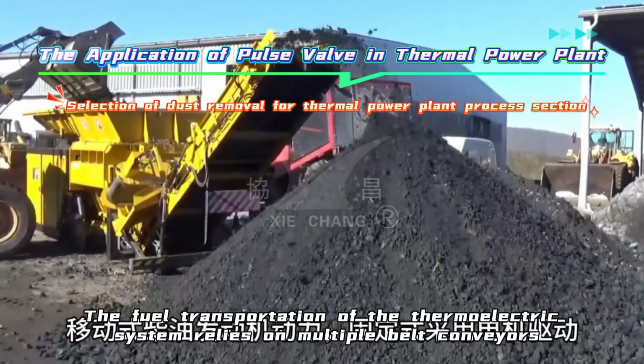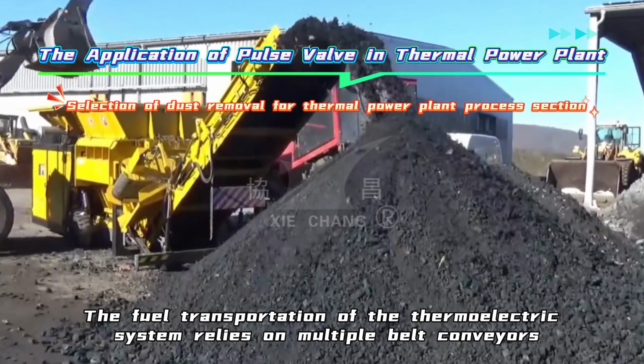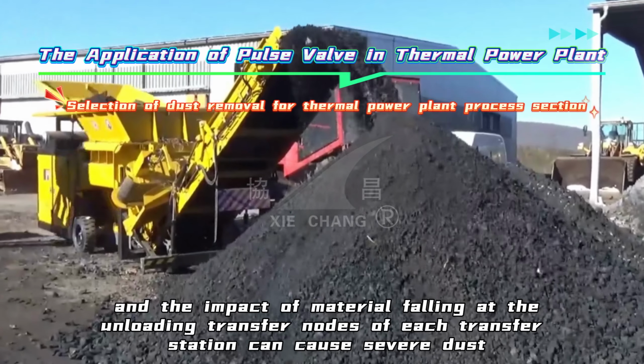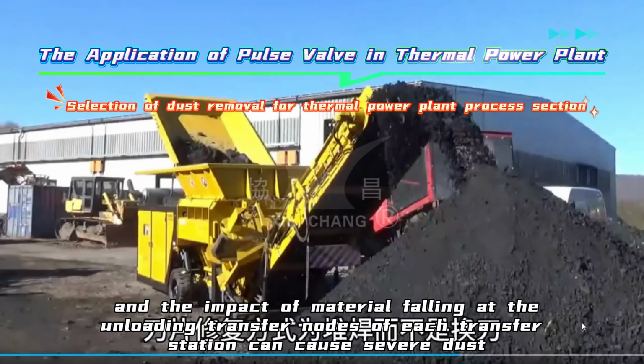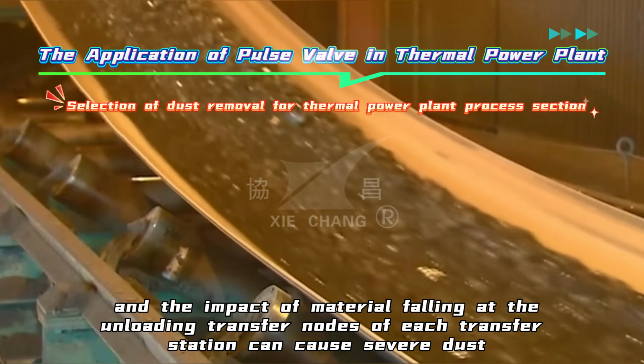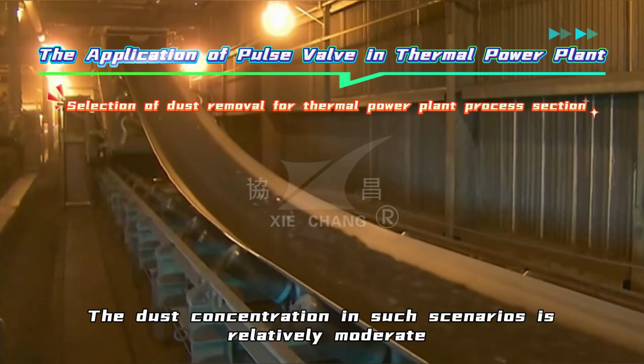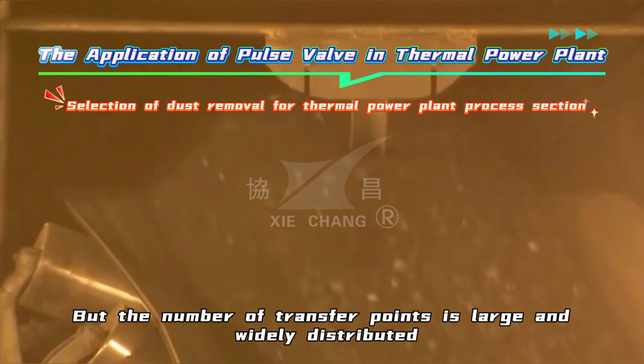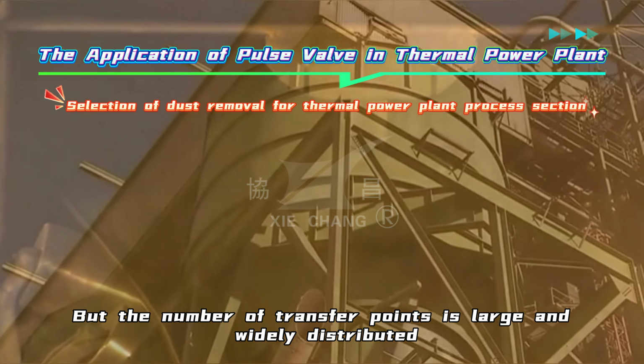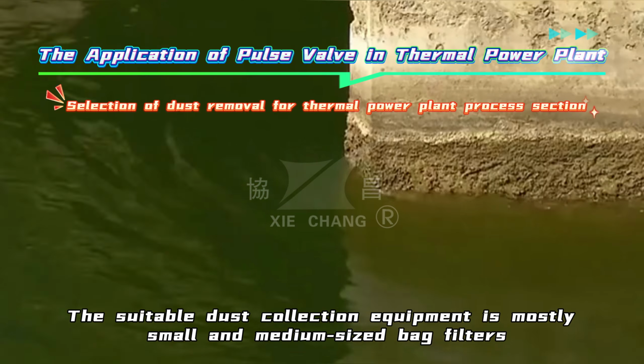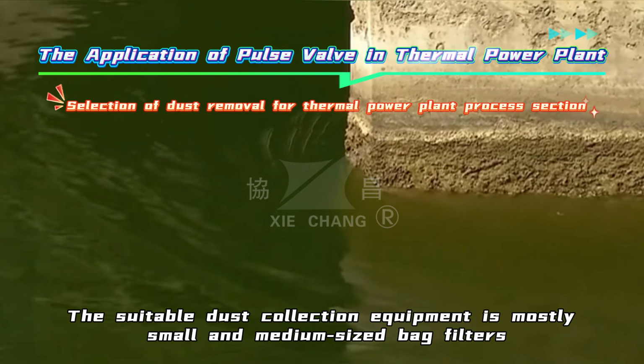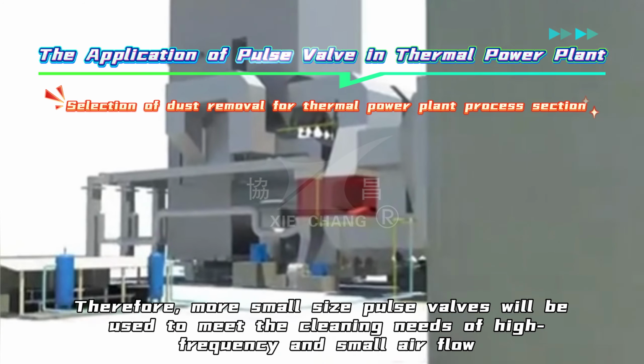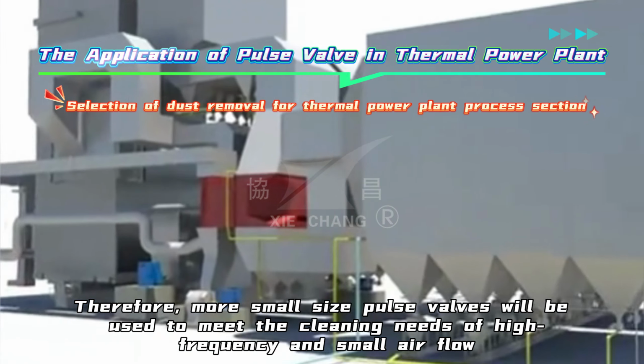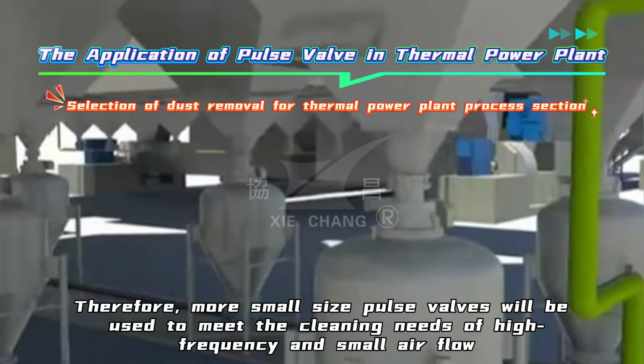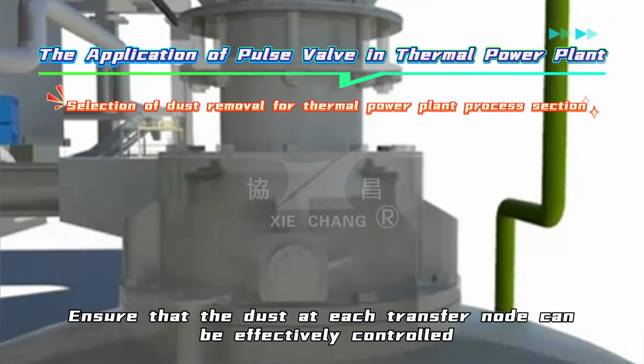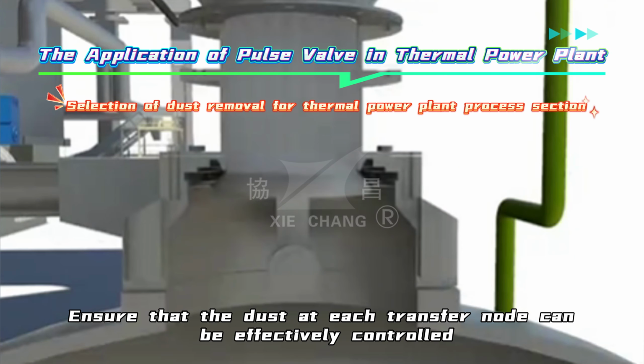The fuel transportation of the thermoelectric system relies on multiple belt conveyors, and the impact of material falling at the unloading transfer nodes of each transfer station can cause severe dust. The dust concentration in such scenarios is relatively moderate, but the number of transfer points is large and widely distributed. The suitable dust collection equipment is mostly small and medium-sized bag filters. Therefore, more small-sized pulse valves will be used to meet the cleaning needs of high frequency and small airflow. Ensure that the dust at each transfer node can be effectively controlled.